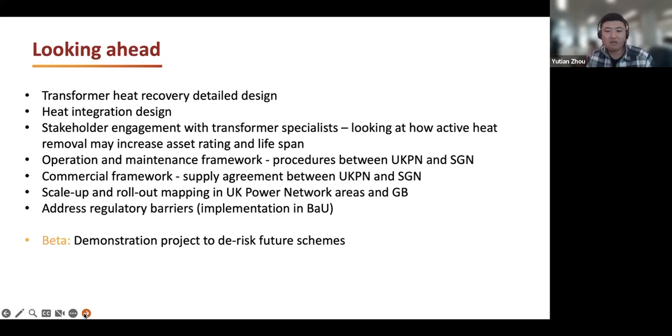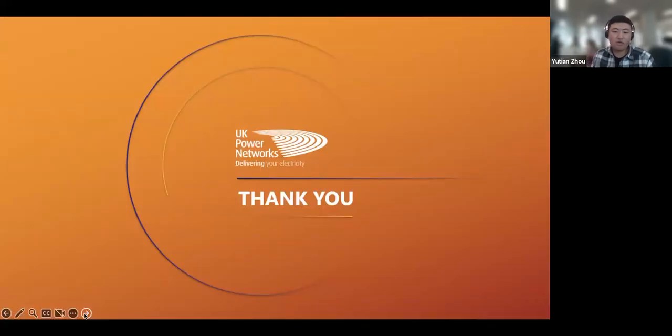Next, UKPN would try to engage with Ofgem to explore the potential regulatory barriers and how we can implement the DNO selling heat as a business-as-usual scenario. Through Alpha Phase, we'd like to develop the detailed design to a robust stage 3 and prepare the tender documentation, to make sure that in beta phase we can procure design and build contractors to implement the system. If successful, we believe this may be the first heat recovery from transformer project in the UK, and this would demonstrate the potential and help to de-risk future schemes. That's all the slides, and we welcome any questions.